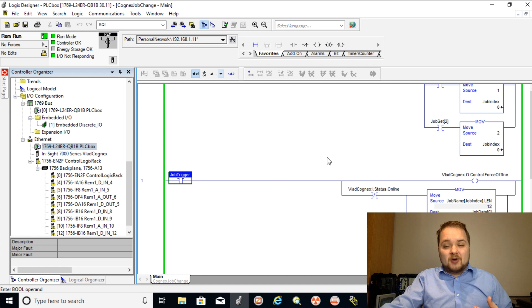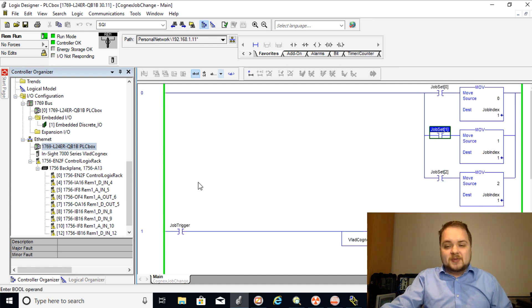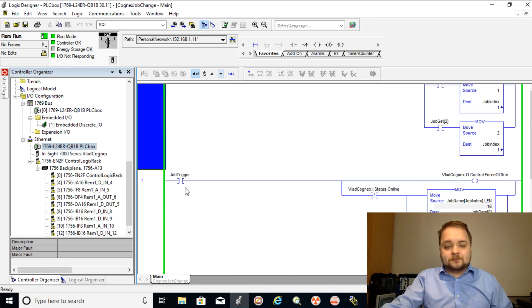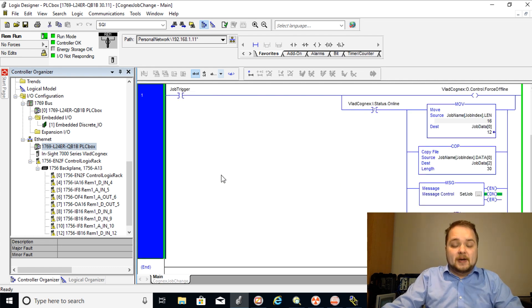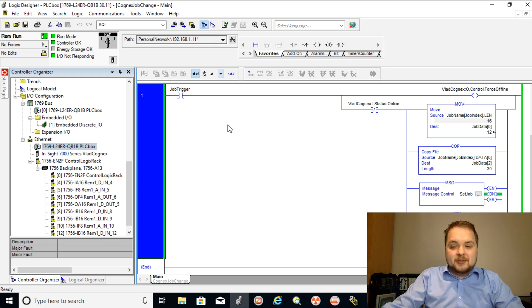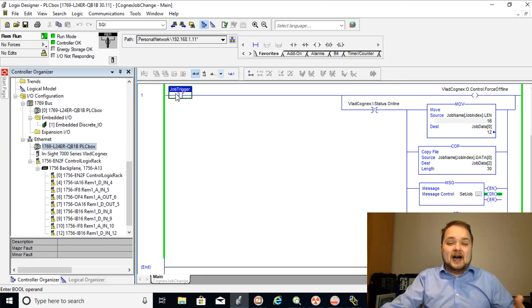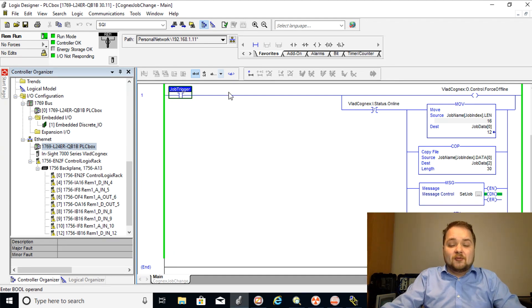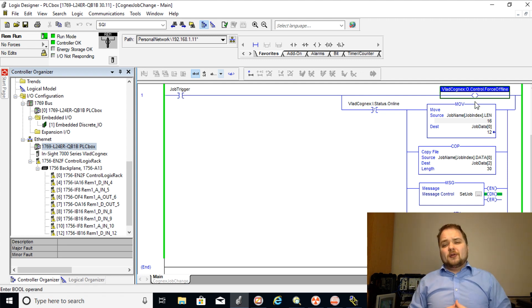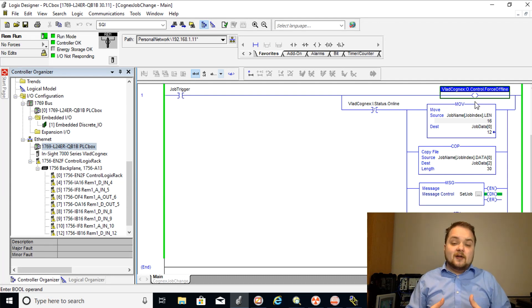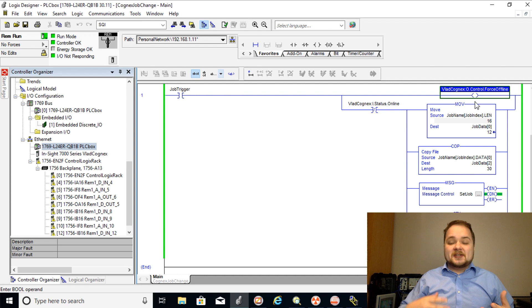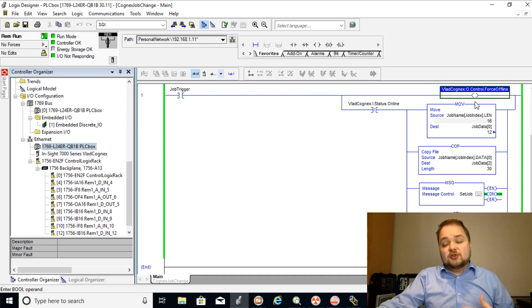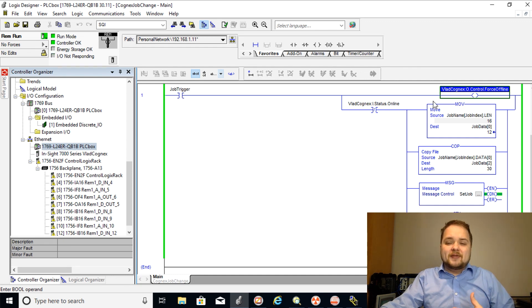Let's look at the program a little bit more closely. We're going to also select the second job to be installed but here's the main rung which you need to understand in order to trigger between different jobs. So the trigger essentially just goes to set off a bit to a high whenever you want to select a different job and immediately this bit will toggle what's called a forced offline bit. So in order for the camera to be able to change jobs it needs to be offline and remember from my previous videos the online state essentially allows the camera to process images as it normally would in production. In order for it to take any changes into effect it does need to be offline.